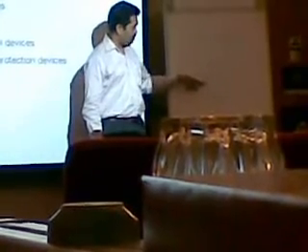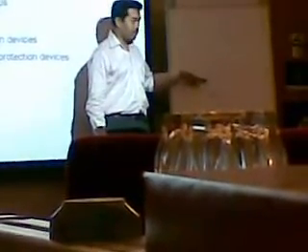Discrimination in the sense, we have total discrimination or partial discrimination. Definitely, in all places we may not achieve total discrimination at all levels. That is why there is total discrimination or partial discrimination. What is total discrimination? When there is a fault, the immediate upstream trips and this doesn't trip. This is called total discrimination.